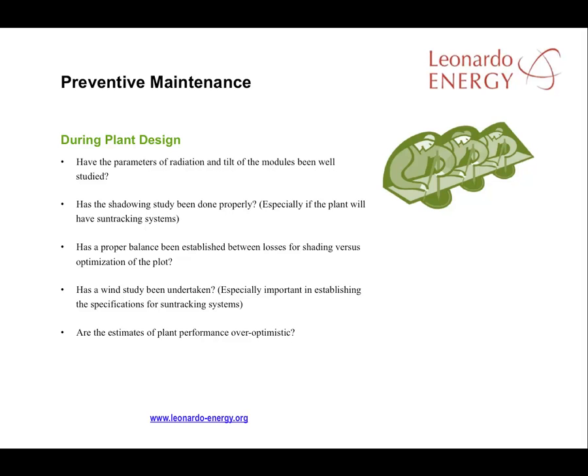There are 10 questions to be considered from a preventive maintenance point of view during plant design. First, are the radiation parameters on the site and the required tilt of the modules well understood? Over-optimistic performance expectations from the site will lead to over-optimistic economic expectations. Second, has a proper shadowing study been carried out that balances shading losses against plot optimisation?